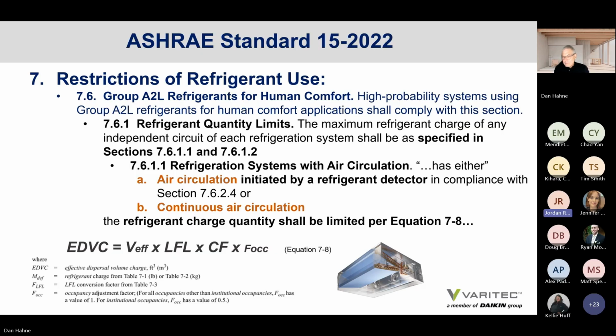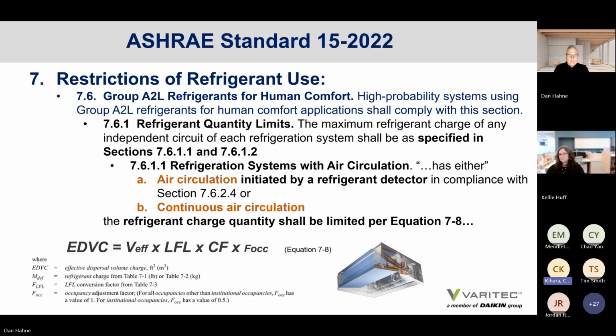Sure. I guess my biggest heartburn though is that, in 34 for R454B, we still list an RCL and an LFL for the A2L refrigerant. Compared to 410A, it went from 26 pounds or something like that down to like 3.4 or 4. That has nothing to do with the LFL. It's just that volumetric calc limit for toxicity or oxygen diffusion. So Daikin has taken the proactive approach of putting built-in SSOVs on the BS boxes, so that MREL calculation now can be.